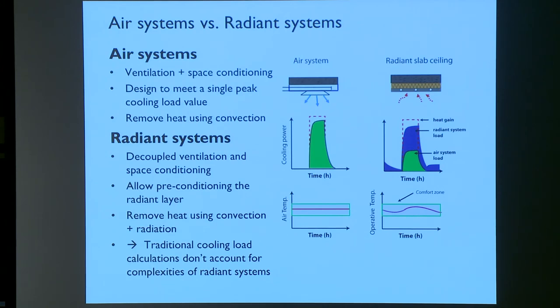So a couple other examples of how they're different: air systems generally operate based on your immediate need - you have heat gain, the system turns on. With radiant systems, especially those with thermal mass, you can spread that conditioning out over time, which has an impact on cost rather than having all your load at the peak part of the day when utility rates are generally higher. You can pre-cool some of the mass. You generally have a bit more floating and a bit less control of the temperature, so it might float over a wider range.